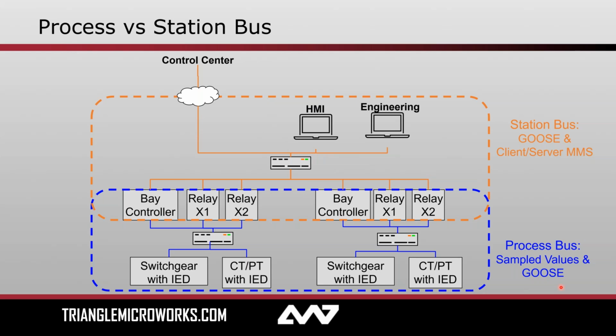They were confusing to me when I first came into this industry. Station bus is this orange box that we see up here at the top. It's a little misleading because technically these IEDs down here might also communicate up with the HMI or client. But when you hear station bus, I want you to think client-server communications like we already spoke about, and GOOSE. When you hear process bus, I want you to think about sample values and, a little bit confusingly, also GOOSE. But if you hear process bus, it will include sample values. So why does this matter? Well, the reason is sometimes there's network segregation in substations where we have two different physical networks, one with process bus information being passed back and forth.